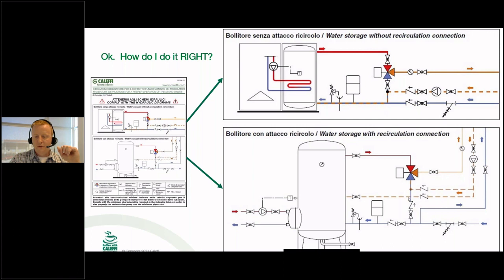You're going to have a check valve just upstream on the cold inlet, and then you're going to have that other guy coming back here to the domestic hot water source, so it can feed right back into the hot inlet and make up for that heat loss in the loop. But again, no balancing now. You don't have to find that really specific scenario, so that way you can get it all set up properly. It's something that you can completely avoid and make your life a lot easier by going with a mixing valve that can prevent that altogether right from the get-go. So definitely something to consider.